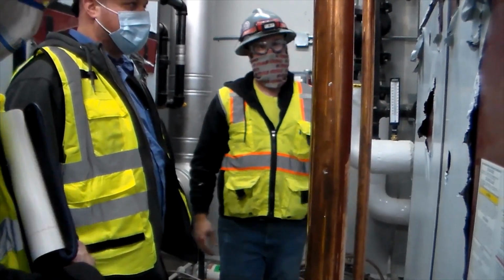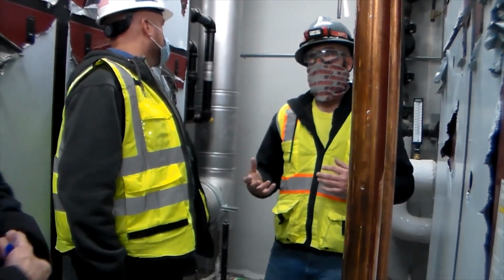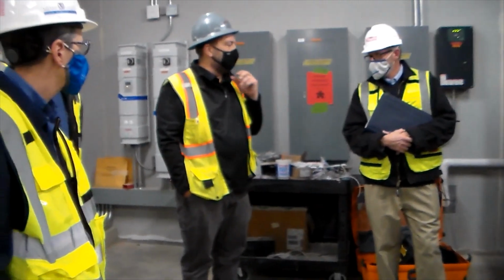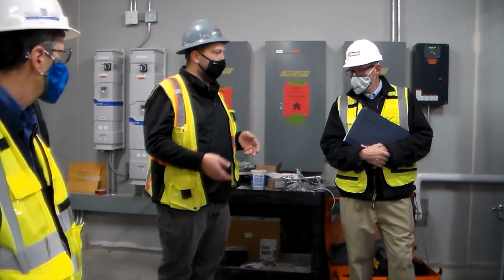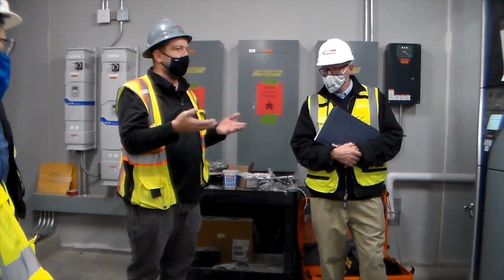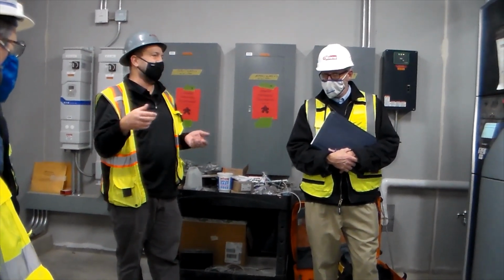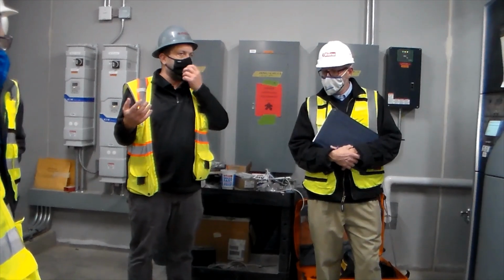Yeah. But Ron might be able to tell you more about the alarms and what they will see on the building automation. So I'll pass it over to him. Yeah, so basically we're sticking to the boiler network over BACnet. When there's alarms or anything like that, it'll all be listed on the graphic. The graphic will show all three of them. It'll light up and show you that number 1 is on, number 2 is the lead. Whatever's the lead, it'll show you. It'll show you who's operating, and also the fire rate, which is something we typically put on. That says how hard the boiler's working.